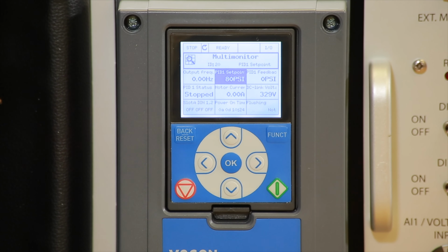So right now we have 0 psi feedback. The lines are empty. So we want to start the motor and see how it goes. So we're going to give it a start command here. So the motor is starting to run. We still have 0 psi and PID status says soft fill. So we're soft filling the pipes at 31 Hertz until we reach a predetermined level. So we're going to keep increasing the feedback until I believe that was 25 psi. And after 25 psi, we go to 60 Hertz. PID loop starts taking over.